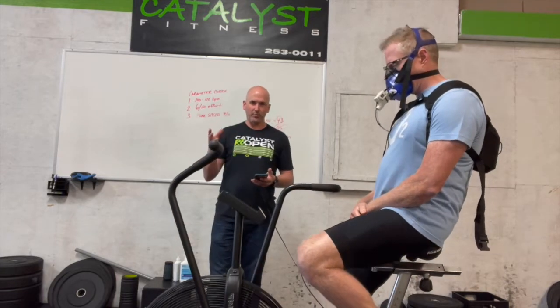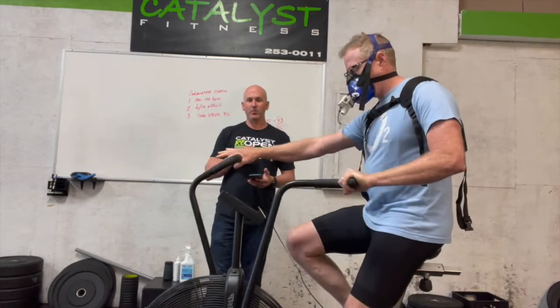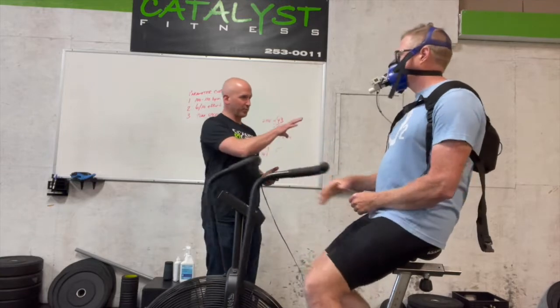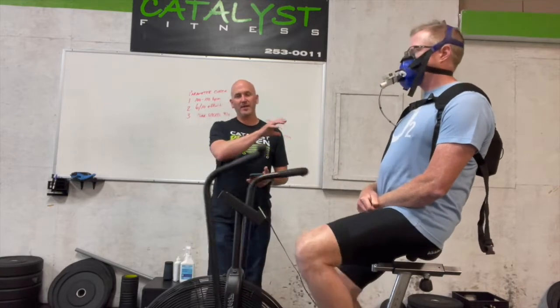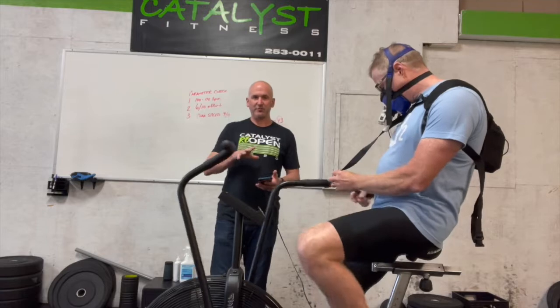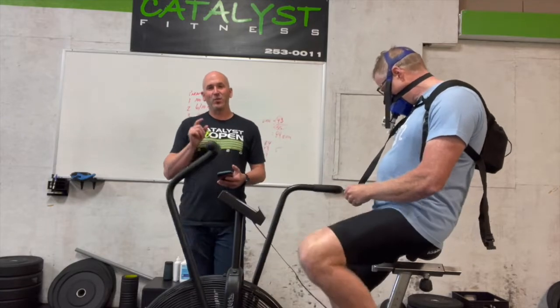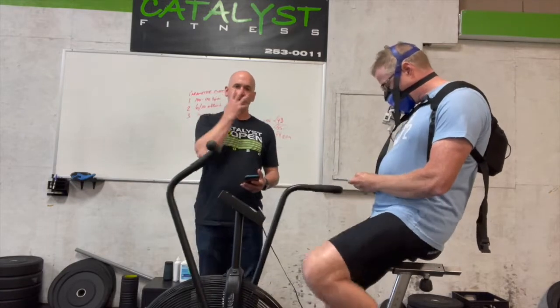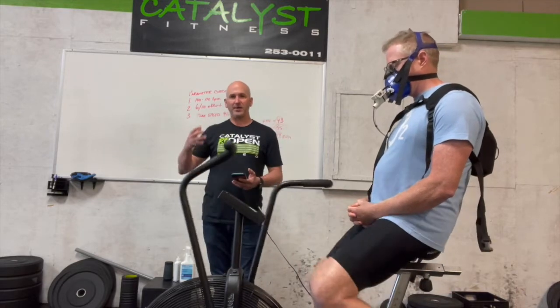Okay, guys, we're going to start Chris's PNOE exercise test now. This should take us about 9 to 12 minutes. One real important thing when you get your athlete ready to go: we've gone through how to set up their test protocol, and we've gotten them all fired up and ready to go for the test. The one thing you want to remember before you get the mask back on your test subject is that you need to calibrate the device without the mask on before they start every test protocol.